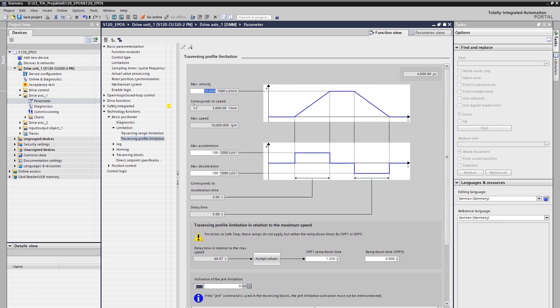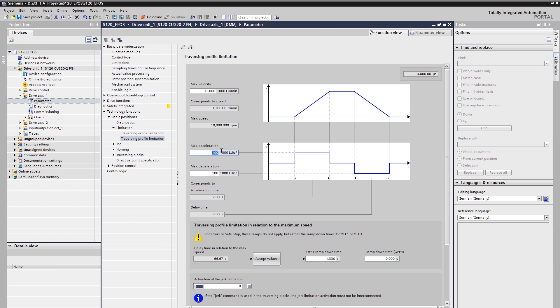Under the limitation of the travel profile, the maximum speed and the maximum acceleration or deceleration are limited on the load side. The basic positioner will not exceed these limits. In the application, the maximum speed of the linear axis should be 12 meters per minute. Since we have chosen a resolution in micrometer, we convert with a factor of 1 million to the value in micrometer per minute and obtain 12 million micrometers or LU per minute. Note, for easier input, the parameter is already normalized to 1000 LU per minute and 12000 is entered here.